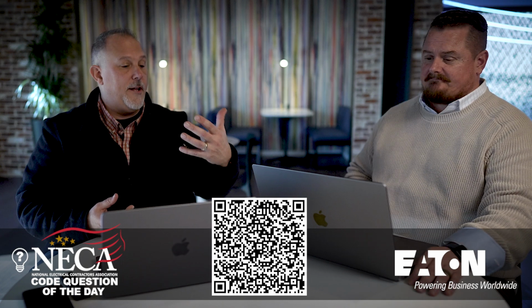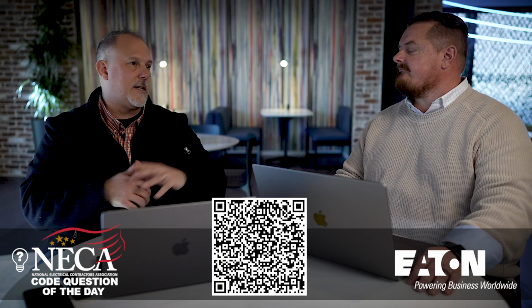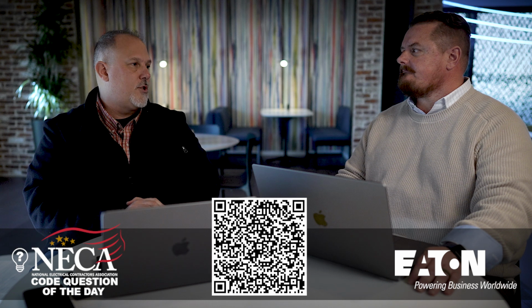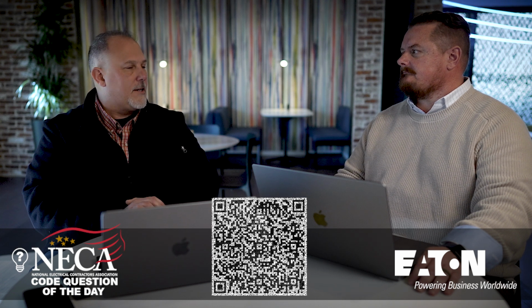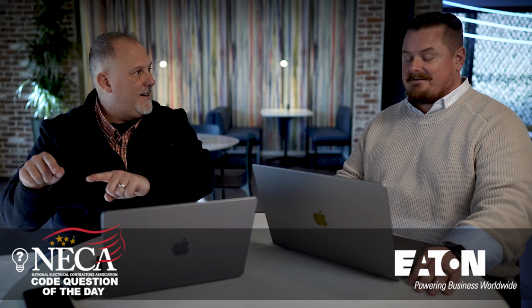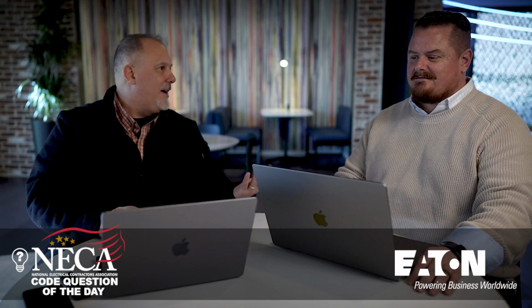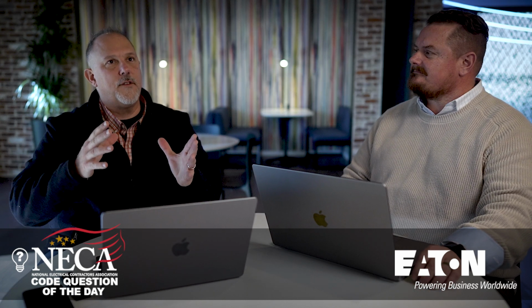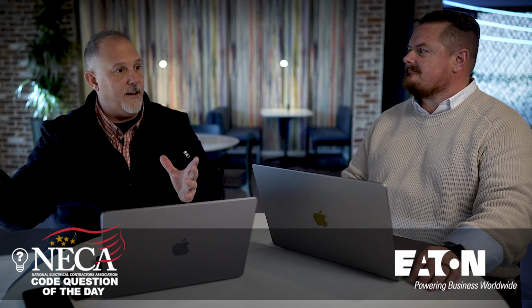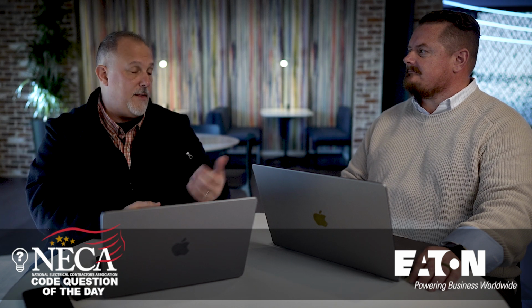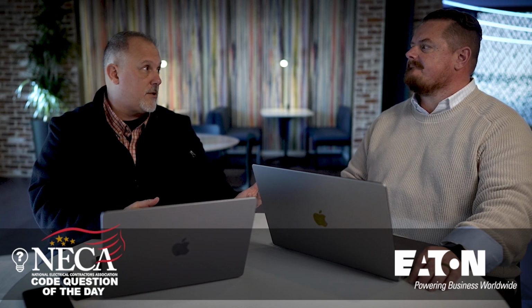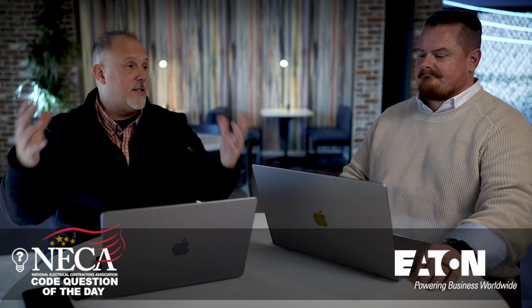Oh yeah. They'll buy a non-fusible disconnect and say, look, it's got a 200,000 amp short circuit current rating. And then I go, well, you have to read the rest of the sentence: when protected by this specific device. Yeah. So then you have to pick the right overcurrent device ahead of it or make it integral with it. And when you get to transfer switches, it's even worse, right? Because now they give you this huge recipe.